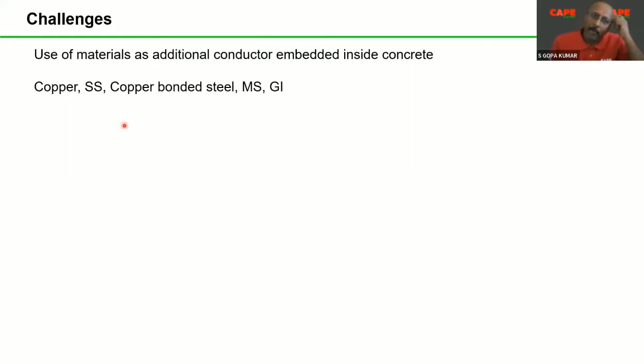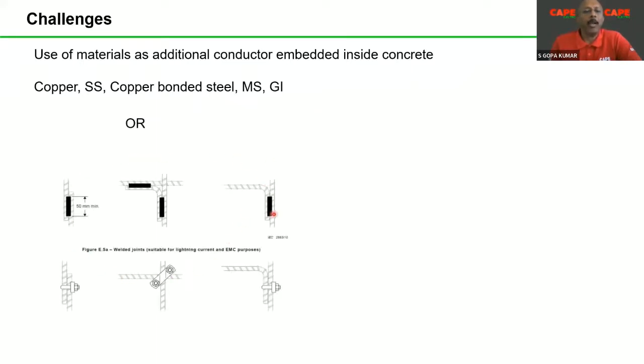The first one: if you read the standard, it allows materials such as copper, stainless steel, copper bonded steel, MS, which means a bare steel conductor, and galvanized steel. All these materials are allowed. But for usage of each of these materials, some specific recommendations are also made in the standard. Similarly, the standard also recommends, or in the picture it is also included, to use the rebar itself. You can use an additional conductor such as copper, stainless steel, copper bonded steel, MS or GI, or you can also use the rebar itself with some kind of special clamping, special welding and so on.